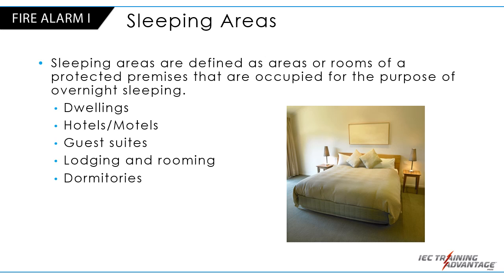And the reason we bring this up is because there are different requirements for what the audible settings are in a sleeping area and the visual settings are in a sleeping area than, say, maybe a corridor. And most of that is measured at the pillow level. Meaning, is it visible from the pillow level? Is it audible or hearable at the pillow level?